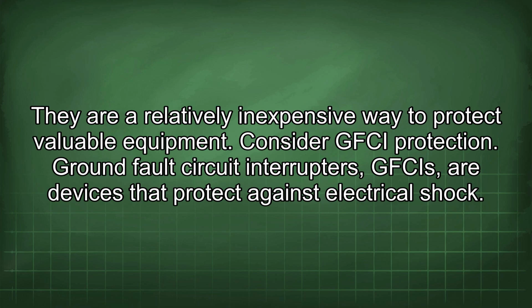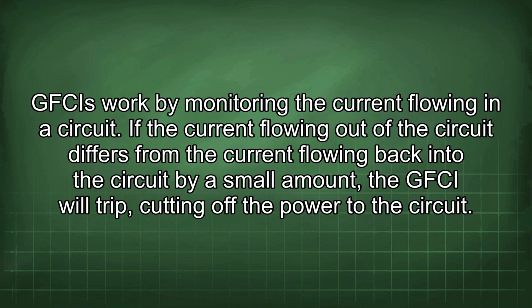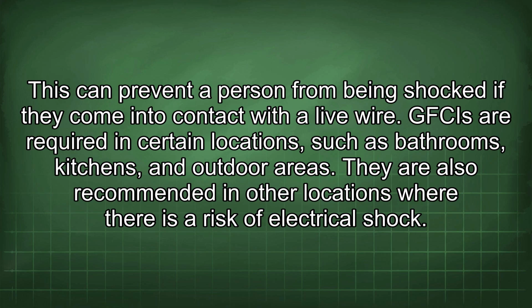Consider GFCI protection. Ground fault circuit interrupters, GFCIs, are devices that protect against electrical shock. GFCIs work by monitoring the current flowing in a circuit. If the current flowing out of the circuit differs from the current flowing back into the circuit by a small amount, the GFCI will trip, cutting off the power to the circuit. This can prevent a person from being shocked if they come into contact with a live wire. GFCIs are required in certain locations such as bathrooms, kitchens, and outdoor areas. They are also recommended in other locations where there is a risk of electrical shock.